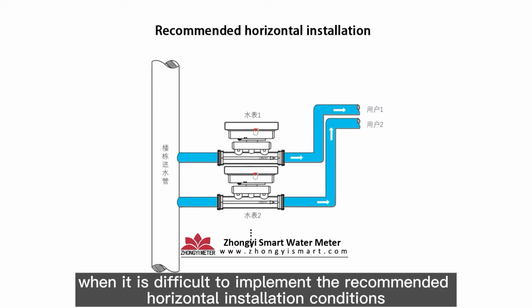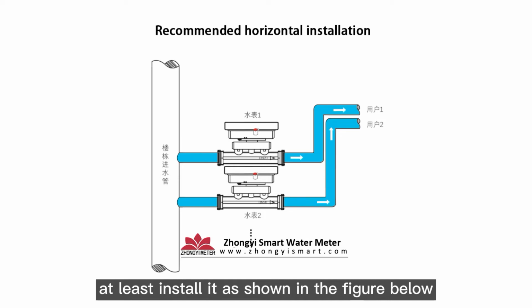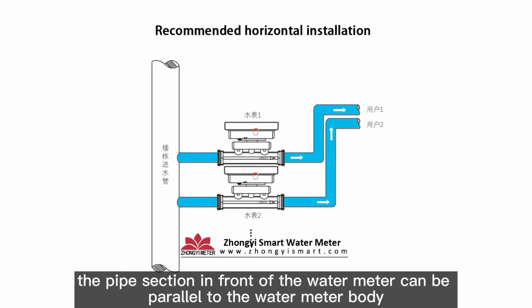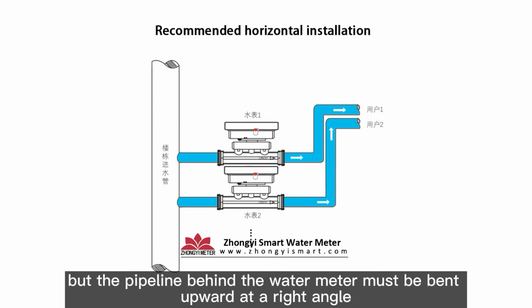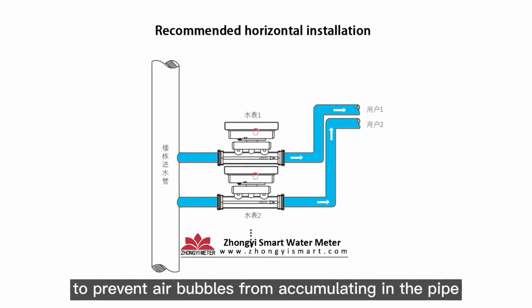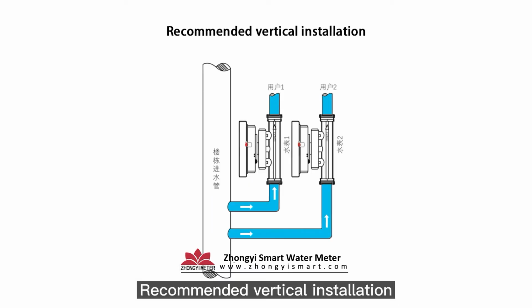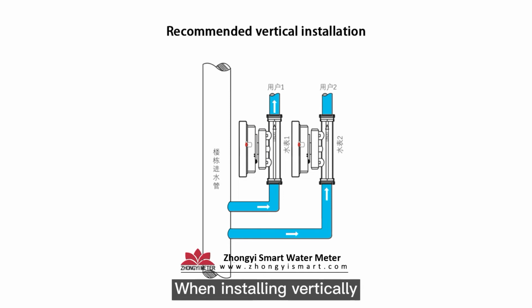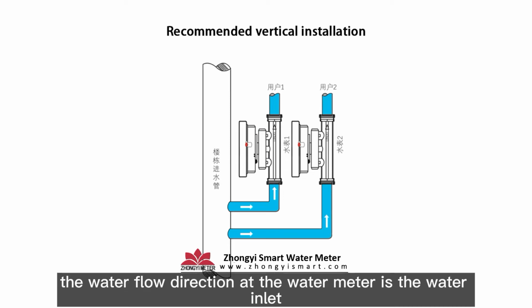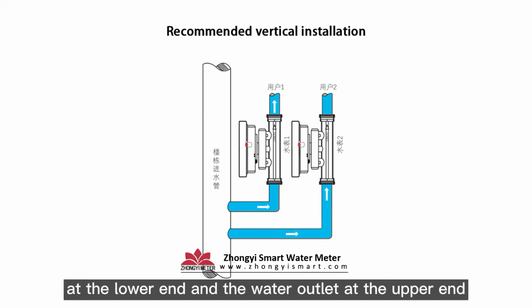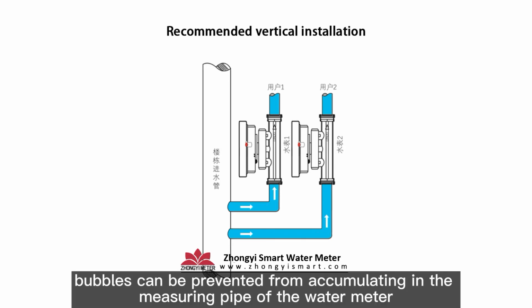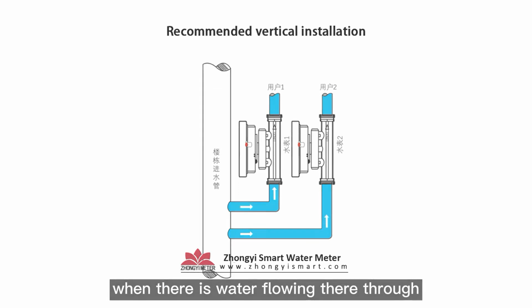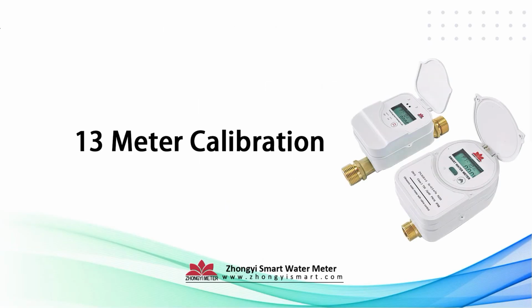When it is difficult to implement the recommended horizontal installation conditions, at least install it as shown in the figure below. In the figure, the pipe section in front of the water meter can be parallel to the water meter body, but the pipeline behind the water meter must be sent upward at a right angle to prevent air bubbles from accumulating in the pipe. Vertical installation is also recommended. When installing vertically, the water inlet is at the lower end and the water outlet at the upper end. In this case, bubbles can be prevented from accumulating in the measuring pipe of the water meter when there is water flowing through. Ultrasonic water meter calibration bench test.